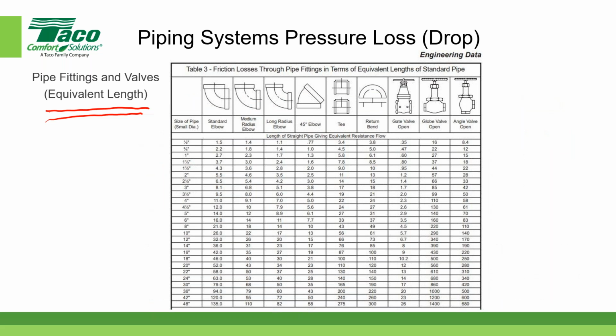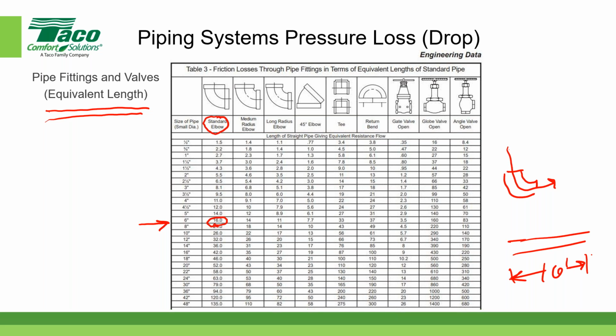So when we talk about using the equivalent length method, we're saying, how much pressure drop is there in a fitting in equivalent length? More specifically, let's use this example here. We're going to point to this 6-inch diameter pipe. And for a standard elbow, it has an equivalent length of approximately 16 feet. Can you see that okay, Brett? I know the lettering is a little small. I can see it. So in other words, if I had a standard elbow, my handy dandy little sketch here, it would have the same pressure drop through that elbow as if it was going through a 16-foot section of pipe. If I had a section of pipe that was 16 feet long, the pressure drop across this little elbow would be equivalent to the pressure drop across 16 feet. And let me put 16 feet there.